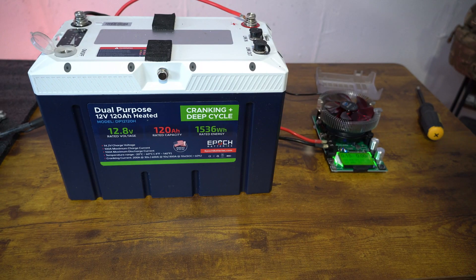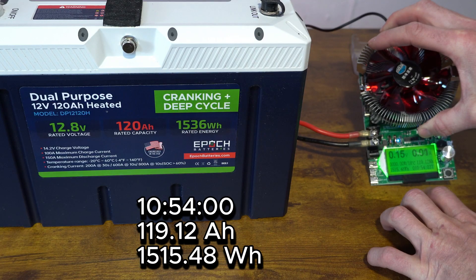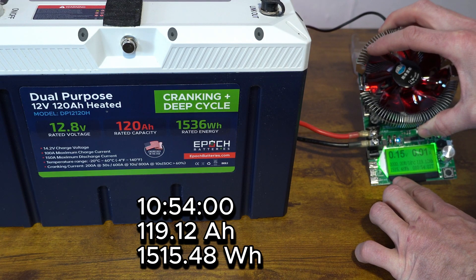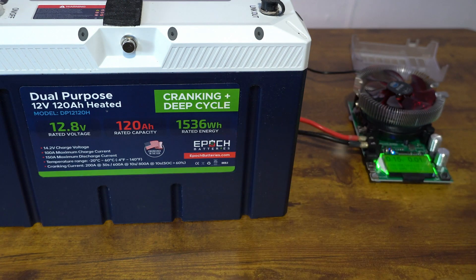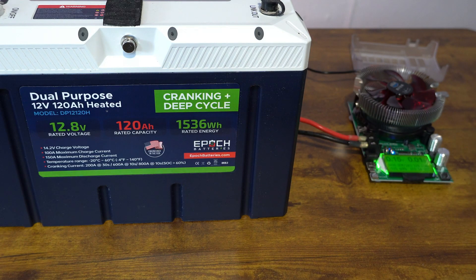The results are in. After 10 hours and 54 minutes, we have 119.12 amp hours and we hit 1,515.48 watt hours. That's not too bad for an entire year of use, considering this is a 120 amp hour, 1,536 watt hour rated battery, and this has a full — let's say 10 months of solid use on it.